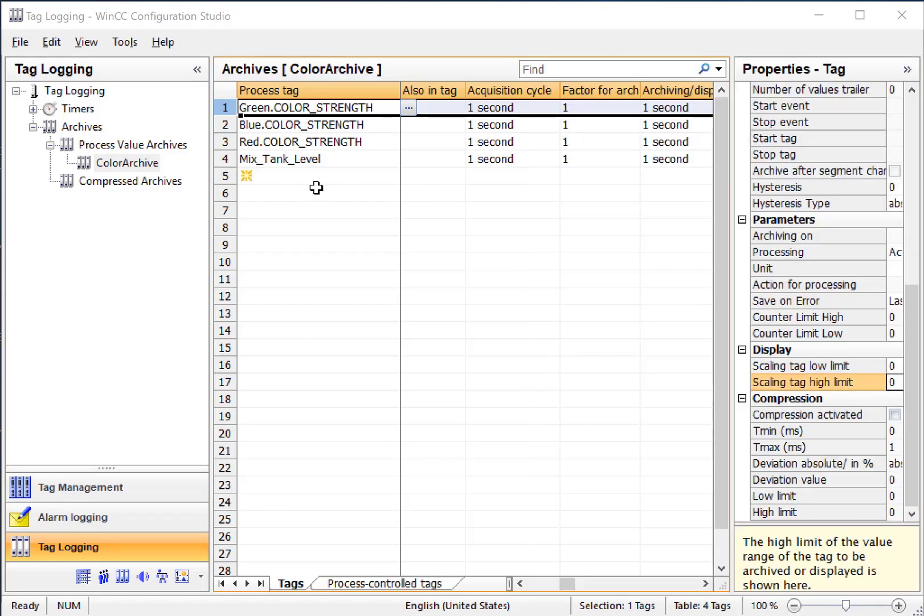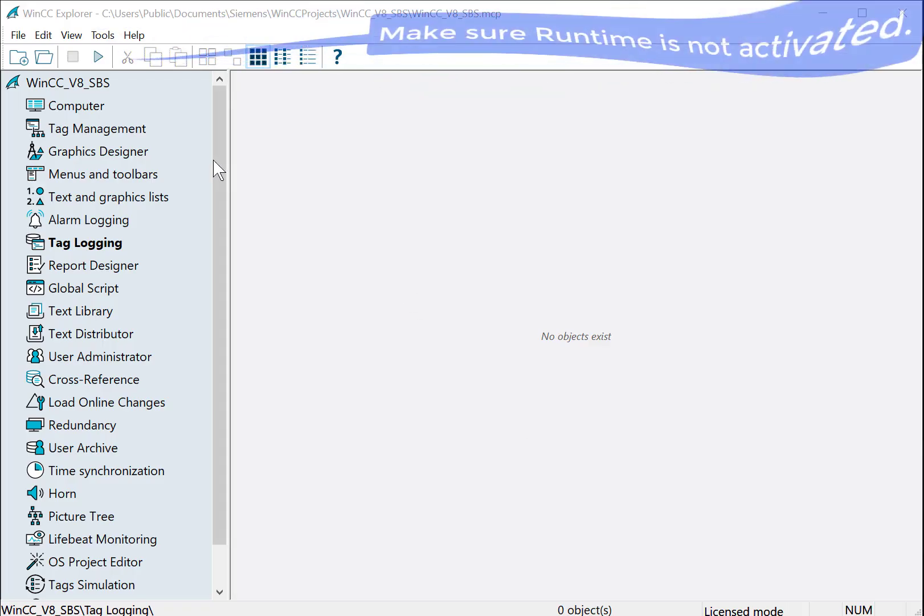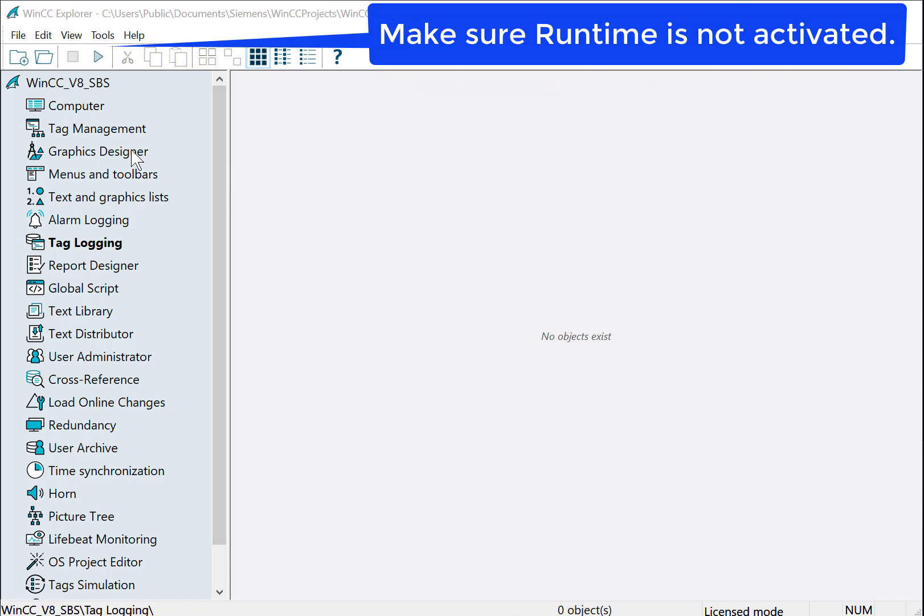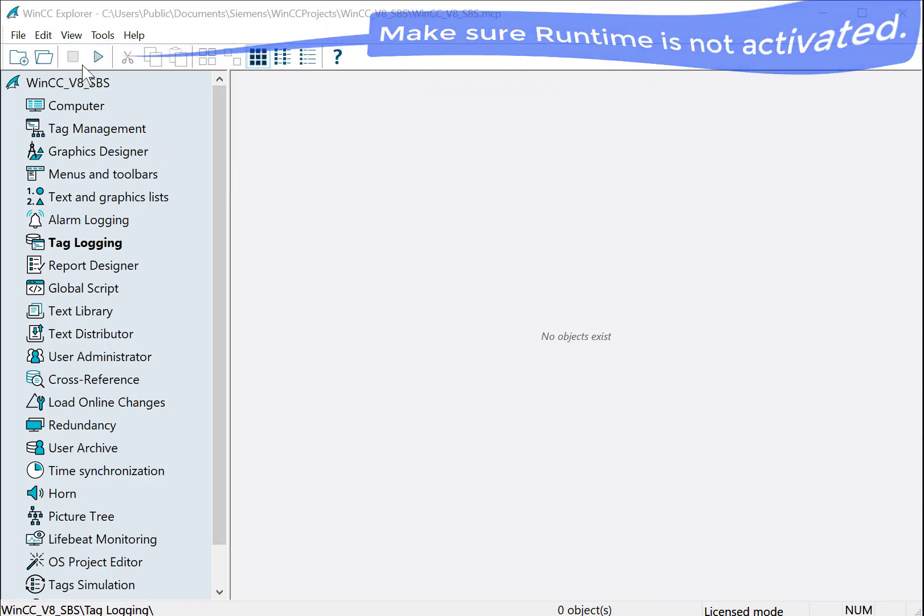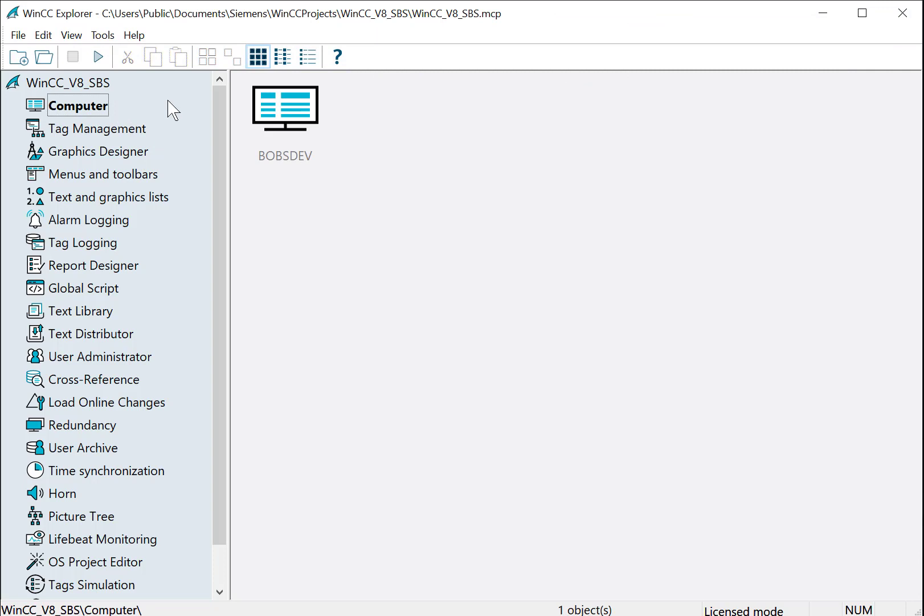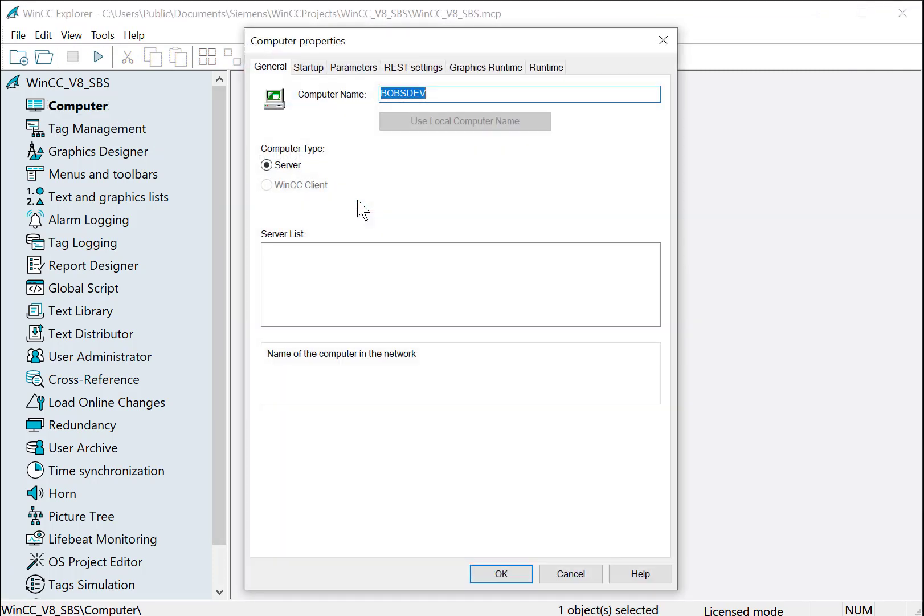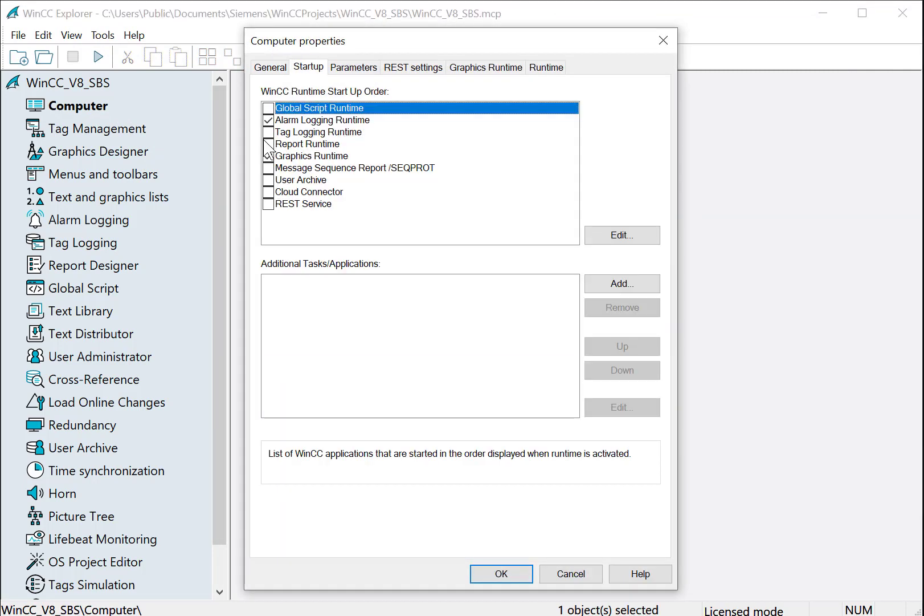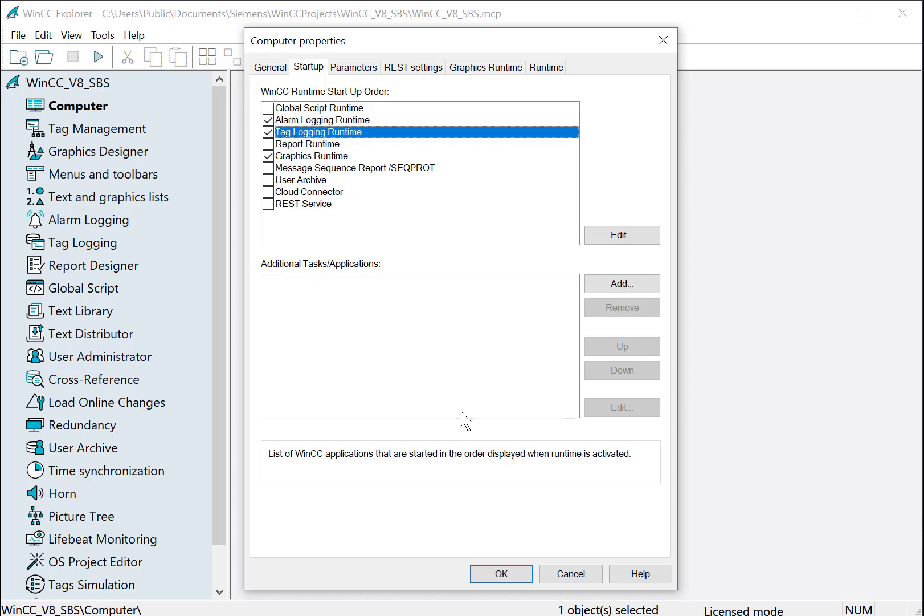So, now that we have our archive created, we will go back to WinCC Explorer, make sure that we're not in runtime, and access the properties of our server. On the startup tab, we're just going to select Tag Logging Runtime, and just click OK.